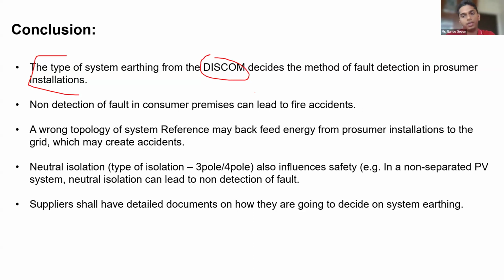But that won't be possible in the PV area. So here they will be trying to find if there is a fault, and we are supposed to rectify it as soon as possible. That is the only possible thing in a PV system. If a fault is not detected in a prosumer's premises, it can lead to fire. Normally inverters give an insulation monitoring device, but in most areas they don't provide that. If you don't have that, then it can be complicated. If you don't detect any fault, it can lead to fire accidents.